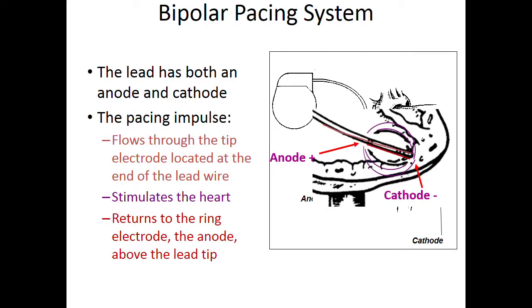Does the patient know when the battery goes dead? Well, these days, what we do is we follow these devices, and when we interrogate them using the programmer, it will actually tell us how much battery life is left. Now, in rare cases, if somebody has not had good follow-up and the battery actually is totally depleted, then yes, they will no longer have pacemaker function. But as long as you're following up, we should definitely know when the indication is to replace the battery. The programmer will actually tell us how much life you have left on it.